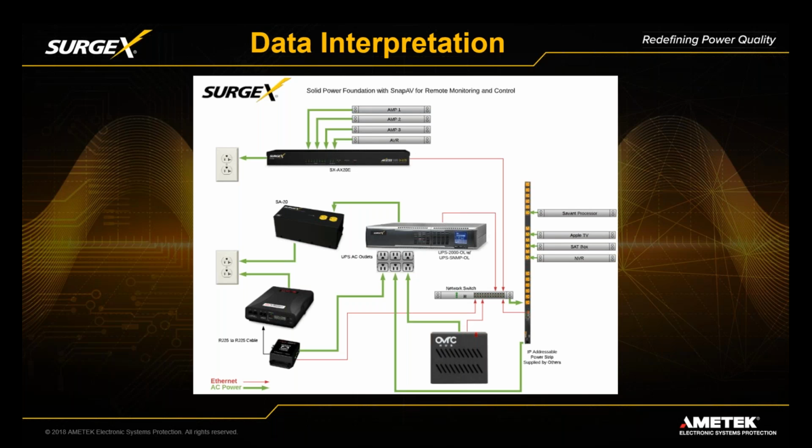And then as you see in the illustration, we've utilized enVision, and we're keeping enVision on the site. And the real reason for that is if you have an issue next month, 6 months from now, do you really want to start then and try to figure out what the cause of the issue is? Or would you rather be able to assess immediately, was it power related? Question mark. Let's go check the logs. Let's see if last weekend, last week, last month, this last 6 months, we had a pattern of power anomalies or events that might have caused the actual issue with the product.